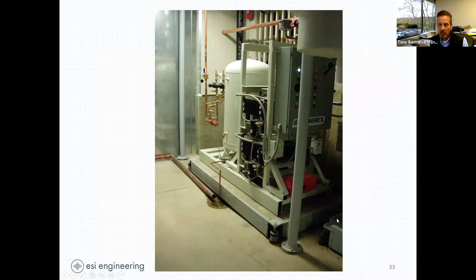right? Everything's well isolated. But when you looked up, you could see the piping from that compressor, sending the compressed air through the hospital, with nice spherical rubber isolators to separate the equipment from the piping to control vibration going into the piping. You see this piece of threaded rod right back here. You follow that up, it goes right up to the underside of the structure. There's actually a steel plate here on the underside of the concrete, and that's a magnetic shield for that MRI to control magnetic fields. But it's bonded right to the concrete. It's right there, and that piece of unistrut or whatever it is is welded to that steel, and that threaded rod goes right up to the underside of that floor.